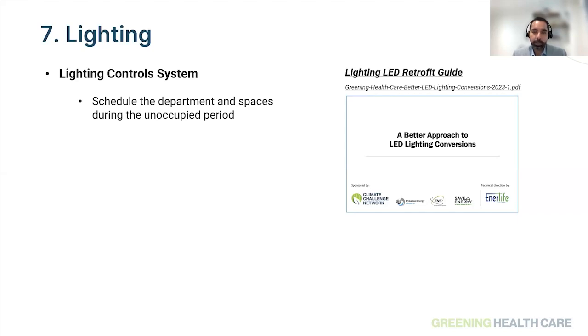And sometimes we find that lighting control systems are there, but they're not fully used, because during the transition from redevelopment to facilities, simple things like login credentials were not shared. So the facility team doesn't have that information and is not able to fully utilize the system. We would recommend you work with your redevelopment teams and make sure the lighting controls are put in. You can use them to schedule the spaces, even dim the spaces as well.